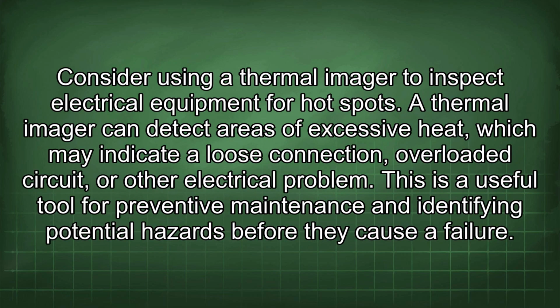Consider using a thermal imager to inspect electrical equipment for hot spots. A thermal imager can detect areas of excessive heat, which may indicate a loose connection, overloaded circuit, or other electrical problem. This is a useful tool for preventive maintenance and identifying potential hazards before they cause a failure.